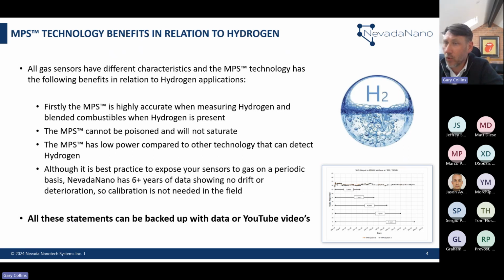The other big area to appreciate is the MPS sensor does not need to be calibrated in the field or within the life of the sensor. There's strong value there, as the sensor will last up to 15 plus years and doesn't need to be calibrated. You can bump test the product from a safety perspective, but there's no need to do a calibration as you would with traditional sensors. Some clients we work with today do a form of bump test to meet local legislation requirements. So that's the key summary on why that's so important.